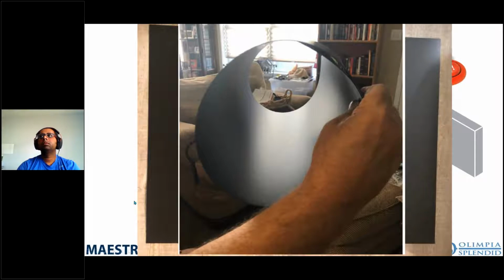So you put a seam across the inside of that, you put a piece of tape, good tape, on the top and bottom of that where it crosses over, and you now have a properly sized duct. You cut the duct about 1.5 inches shorter than the total width, or depth, of your wall from the outside wall to the inside wall, and then you install it. You make sure you keep the seam to the top, and you're done. Your ductwork is finished.